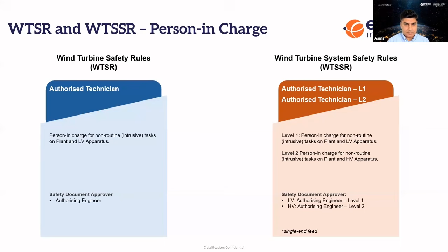Similar to the person in charge, the authorized technician, the person responsible for the creation and approval of the safety document called the approved written procedure is the authorizing engineer under the wind turbine safety rules. On the right-hand side, under the wind turbine system safety rules, we have authorizing engineer level 1 and level 2. The responsibilities for level 1 remain the same as currently under wind turbine safety rules, whereas level 2 will have the ability to create and approve the HV approved written procedure that allows people to work or test on high voltage equipment.